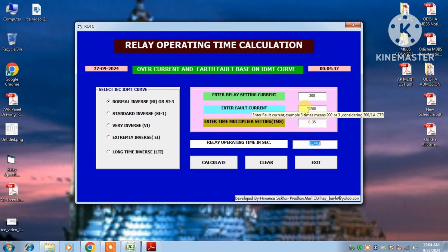If the fault current is 4 times the setting current and the time multiplier setting is 0.35, then that relay will operate in 1.743 seconds. In the same way, if you select the standard inverse 1 or SI1 curve and calculate, it will operate in 0.759 seconds, or 759 milliseconds. Like that, very inverse will also give a time and extremely inverse will also give a time. In each curve we can find different operating times.